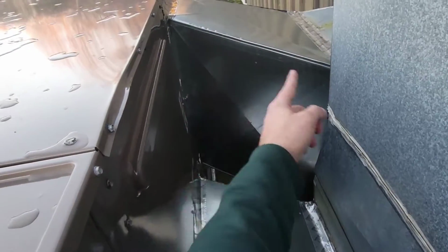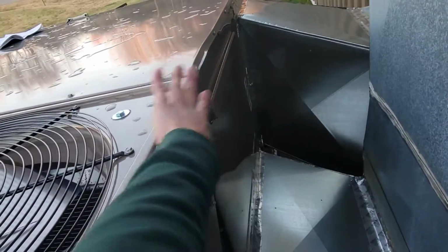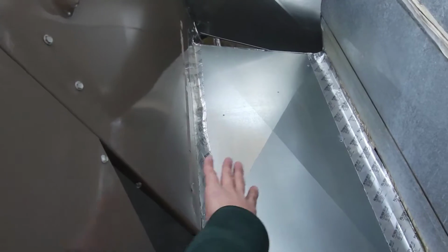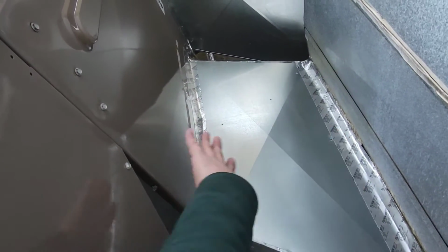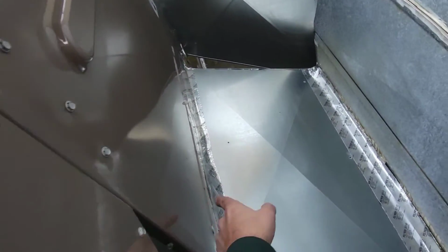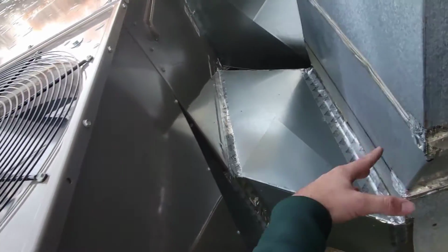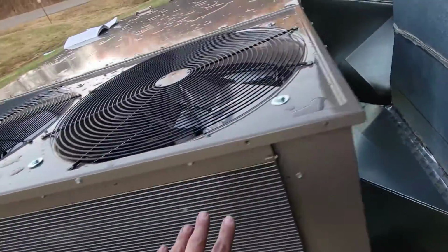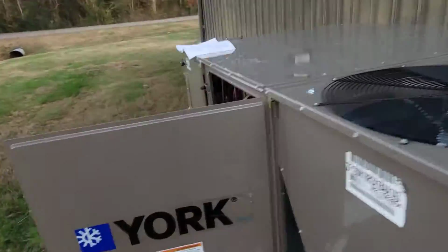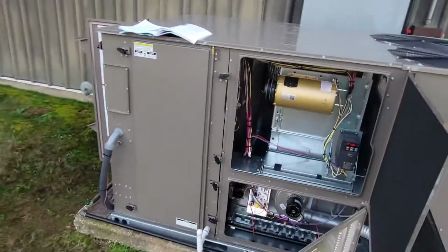This is where the supply hooks up, okay? And this is where the return hooks up. But when this unit was shipped, the side duct covers came on the unit, and the bottom duct covers, which are inside the unit, were off. So this comes shipped, ready to be installed on a rooftop. I need you to know that as well.